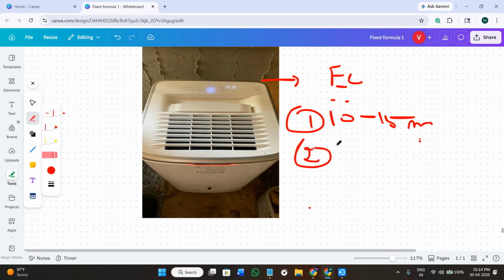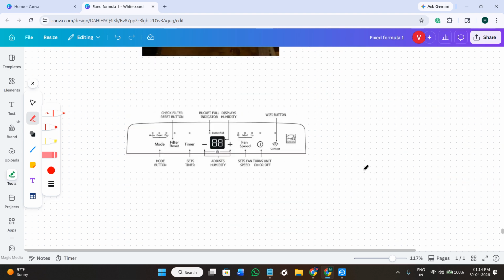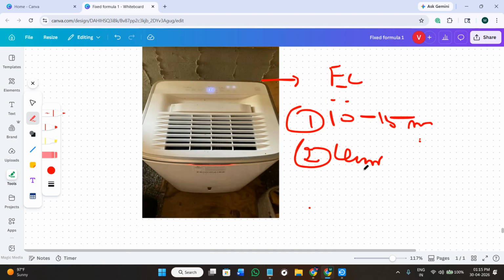After doing so, you just have to simply clean the air filter and the coil. So sometimes the restricted airflow can cause the system to overwork and then trigger the EC warning. So you need to remove its air filter and inspect the evaporator and the condenser coils for dust buildup that may be reducing cooling efficiency.